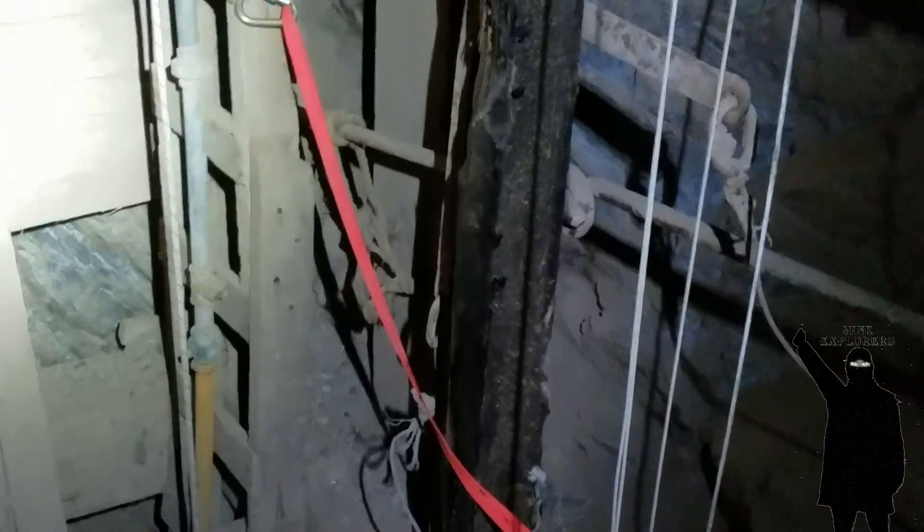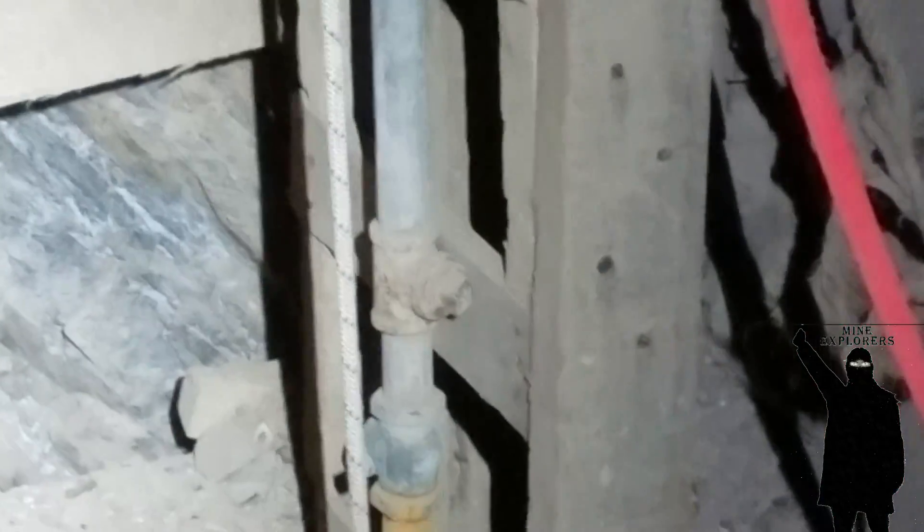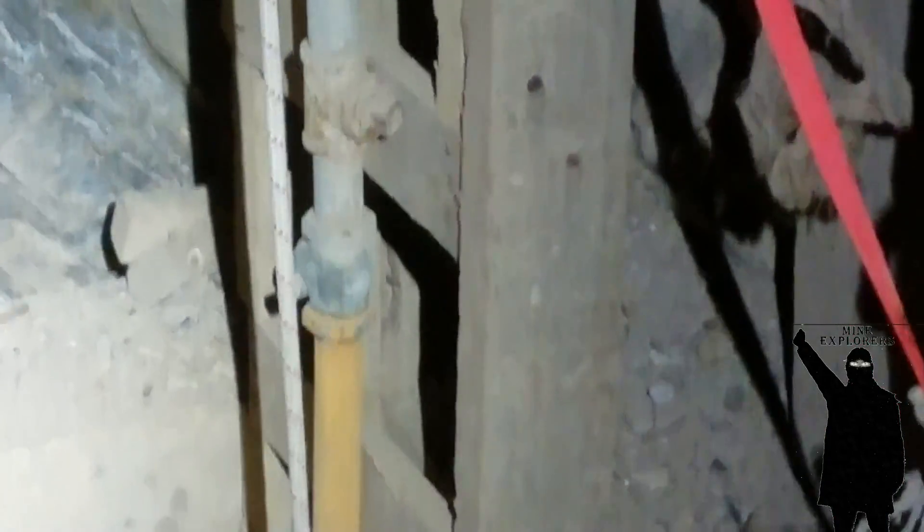We think right here is the failure point. You can see where the pipe has pulled away from the timbering — look at that rust. That looks like that was a valve and the knob blew out — it's just hollow. The pipe has completely pulled away from the timber here and that valve took the brunt of the flex. You can see where the water was just running down.